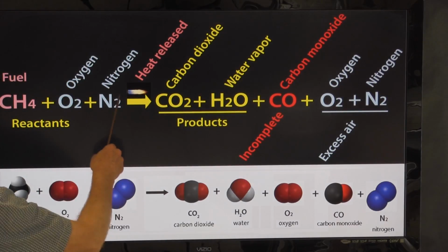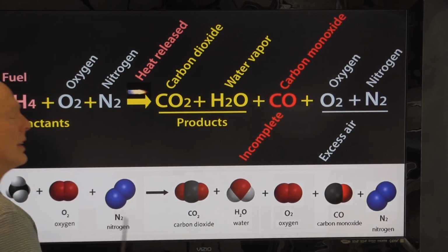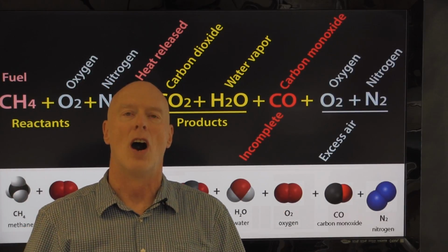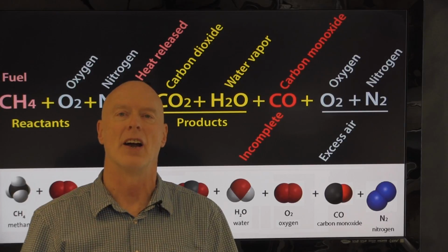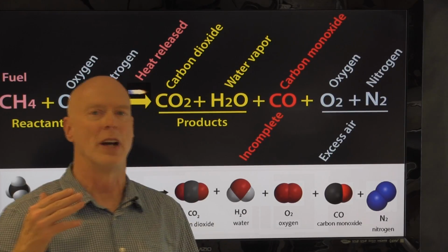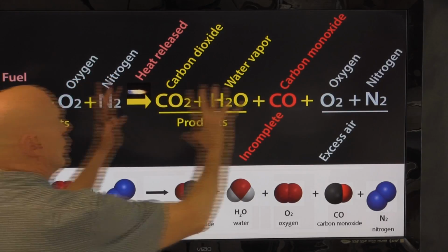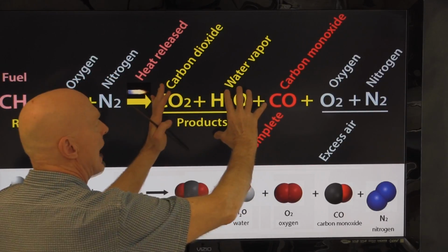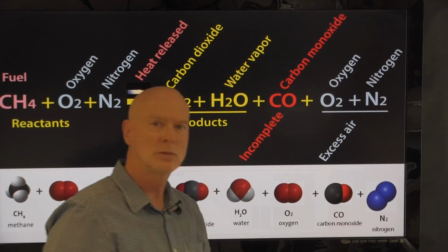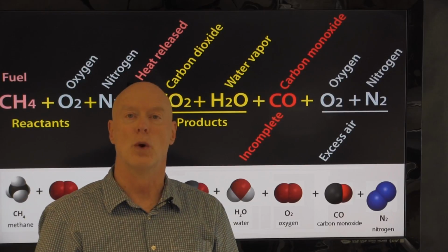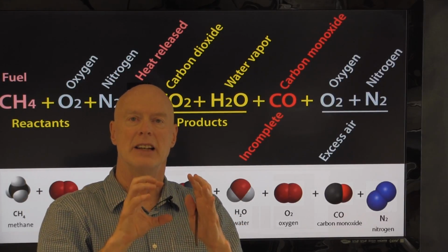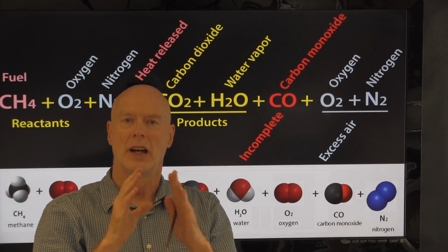Well, we've got oxygen and nitrogen here, and why have I included nitrogen? Well, oxygen and nitrogen are the two components of the air. The air is 79% nitrogen, 21% oxygen. Every molecule of those two gases that goes through this process and ends up over here represents a kind of a waste, because every molecule carries some heat from the flame with it.